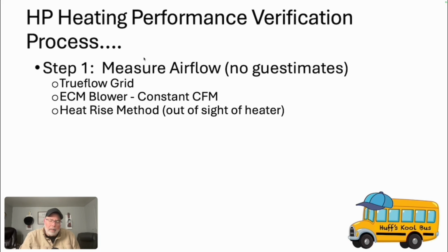I actually called Jim Bergman about doing this video and just wanted to get his take on that. And he said absolutely that the heat rise method is an accurate way. Now, the one thing that's important, and he made note of this when we were talking, is to make sure you tell them that when you measure that supply air temperature, it's got to be out of sight of that heater. So any of you who are MeasureQuick users, we typically place the air probe in the first outlet downstream from the equipment, right? So that very first outlet coming off that duct system. So that's just an important part.